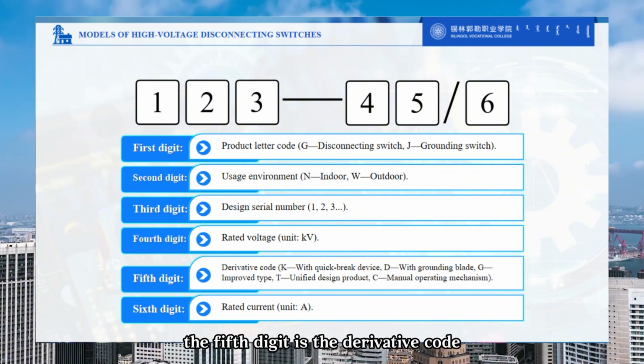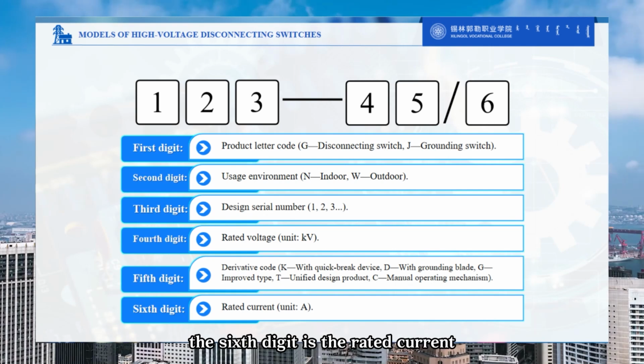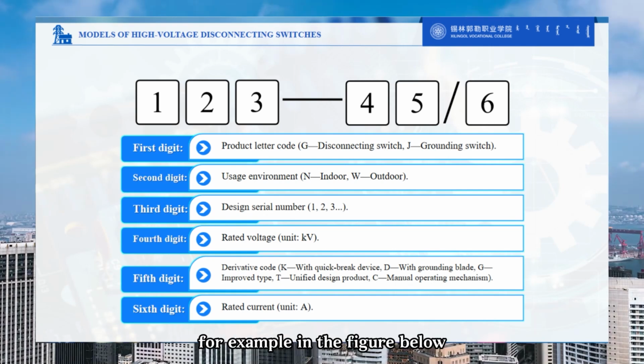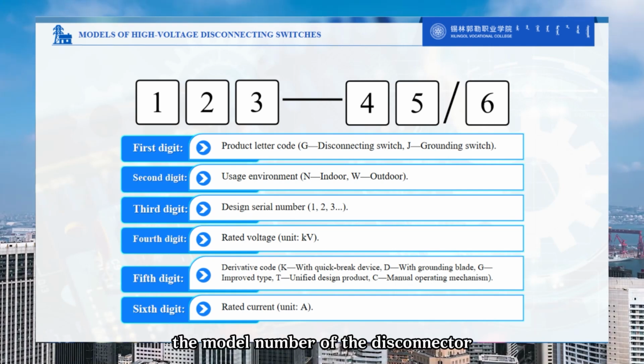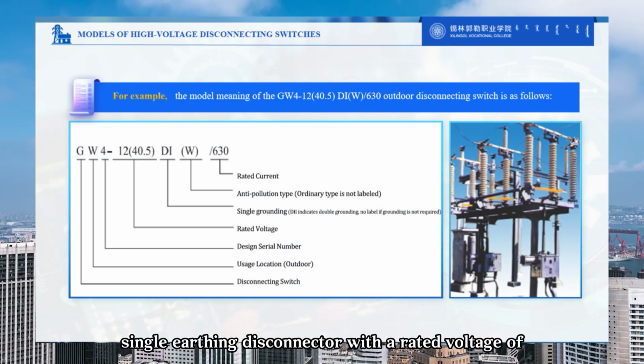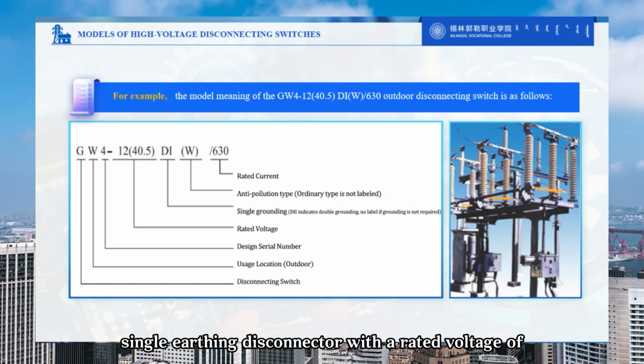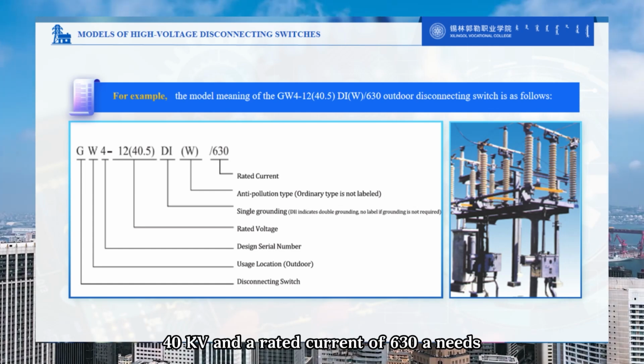The fifth digit is the derivative code. The sixth digit is the rated current. For example, in the figure below, the model number of the disconnector means outdoor double-break single earthing disconnector with a rated voltage of 40 kV and a rated current of 630 A.